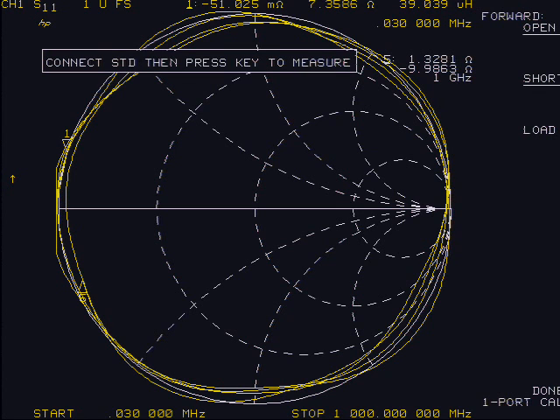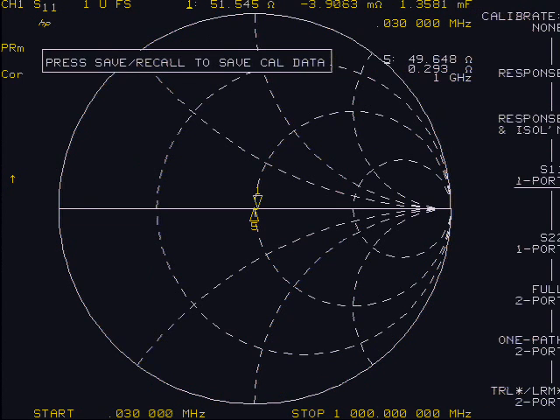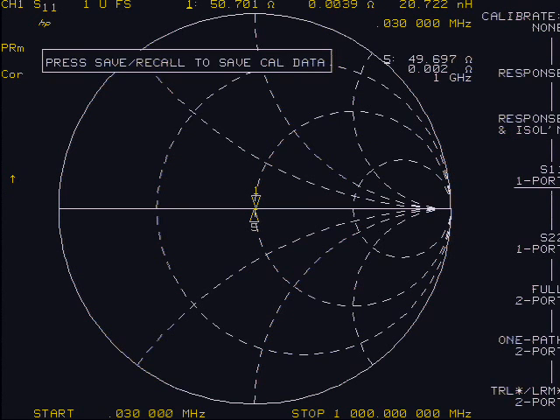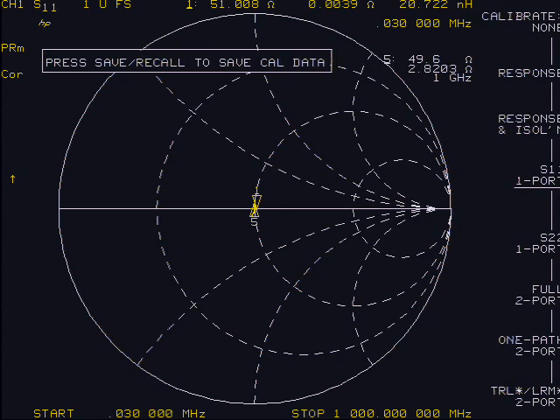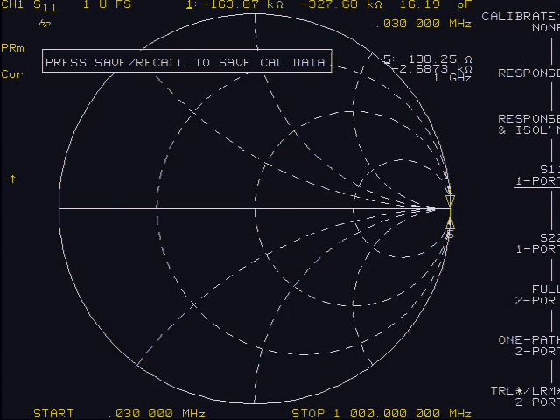At this point, the display should show the two markers indicating the starting and stopping frequencies in almost the same point. The closer these two points are and at the center of the chart for the 50-ohm component, the better your cal data.